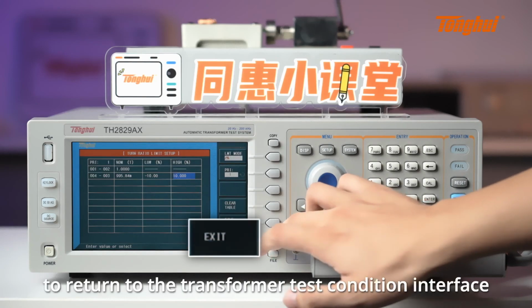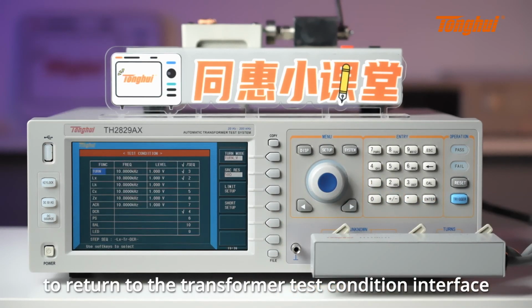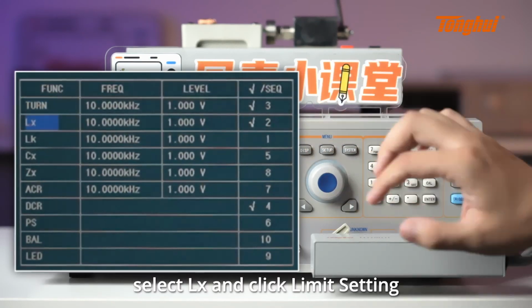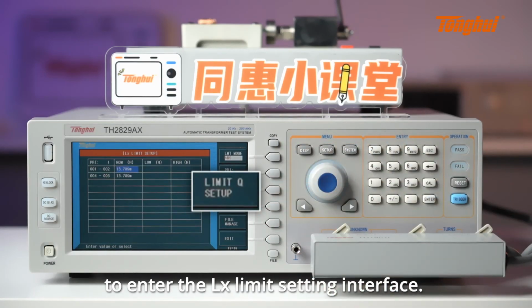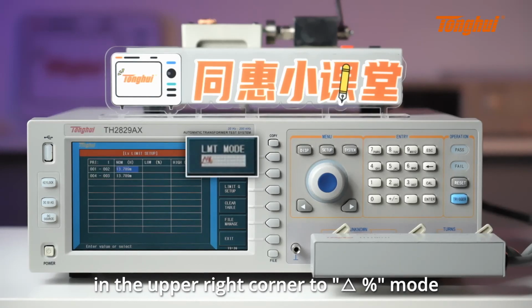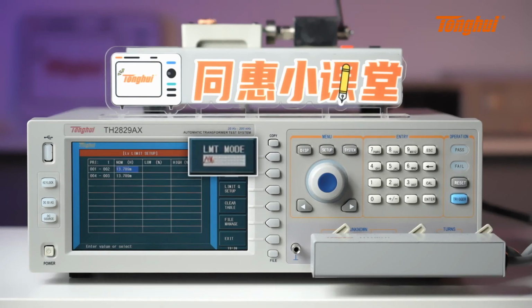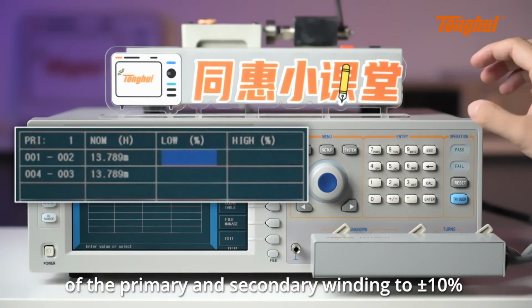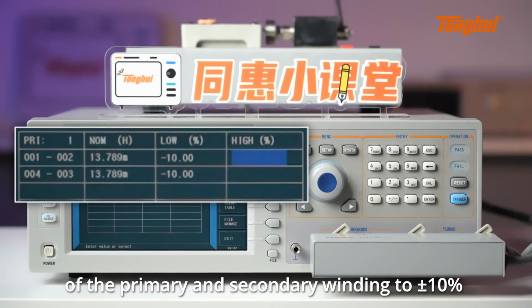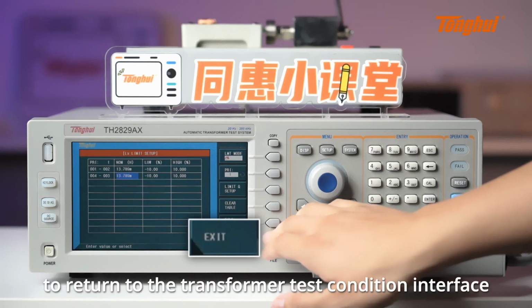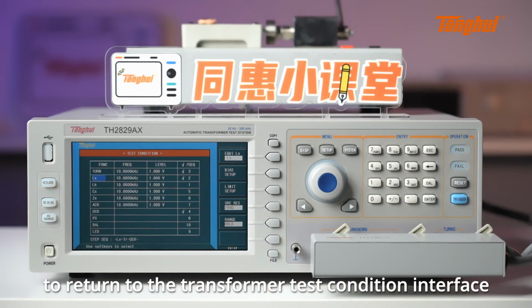Click Exit to return on the transformer test condition interface. Select LX and click Limit Setting to enter the LX limit setting interface. Change the limit mode in the upper right corner to percentage mode and set the upper and lower limits of the primary and secondary windings to negative to positive 10%. Click Exit to return to the transformer test condition interface.